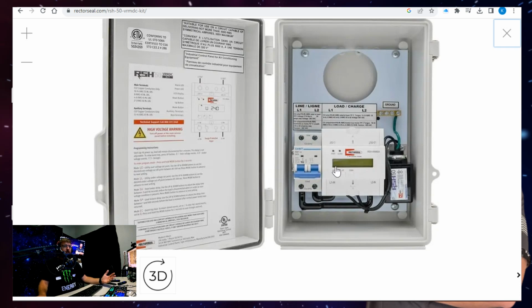So the nice part is you don't have to worry about fuses, but on an inverter system, you can set the minimum voltage on this thing. You can set it down to whatever the lowest manufacturer's rating. So I would probably go a little bit above that. 200 volts, it shuts off. And if it trips, it has a minimum 4-minute protection, or 3-minute. I can't remember exactly. Don't quote me on that. But it has a protection.